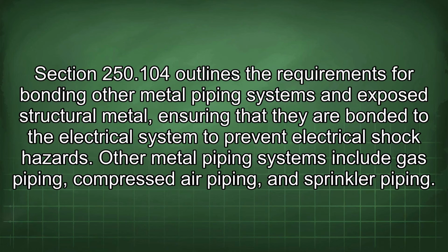Section 250.104 outlines the requirements for bonding other metal piping systems and exposed structural metal, ensuring that they are bonded to the electrical system to prevent electrical shock hazards. Other metal piping systems include gas piping, compressed air piping, and sprinkler piping.